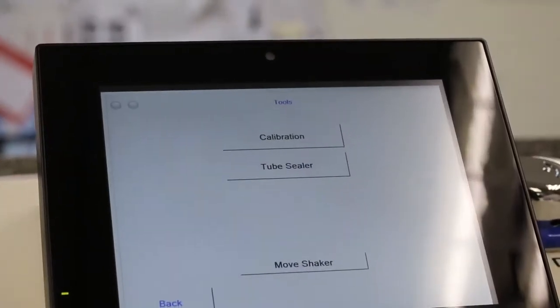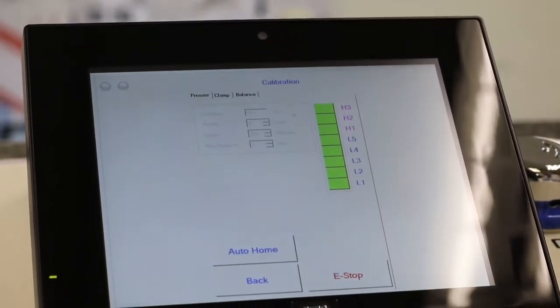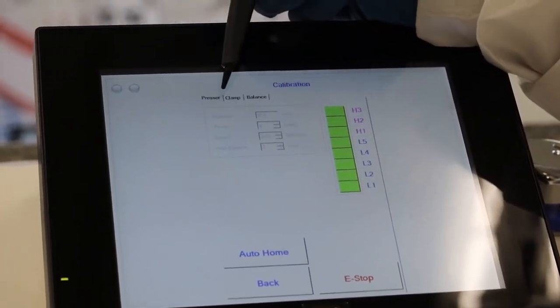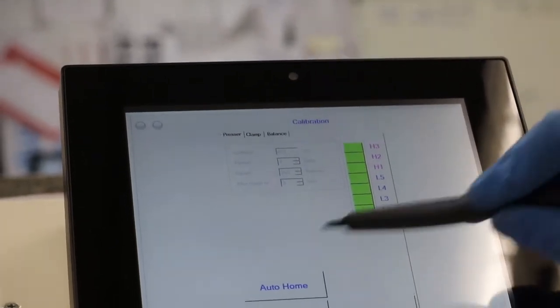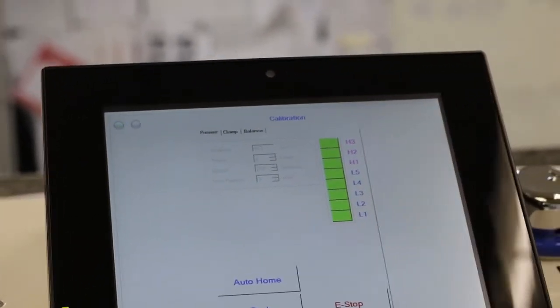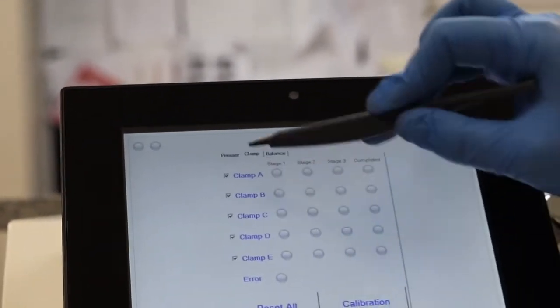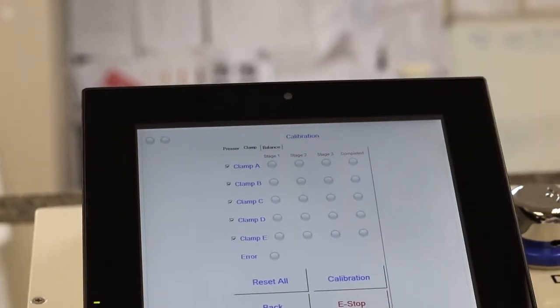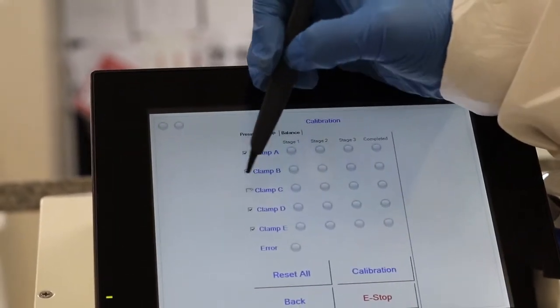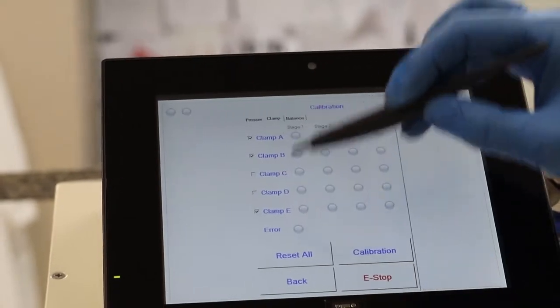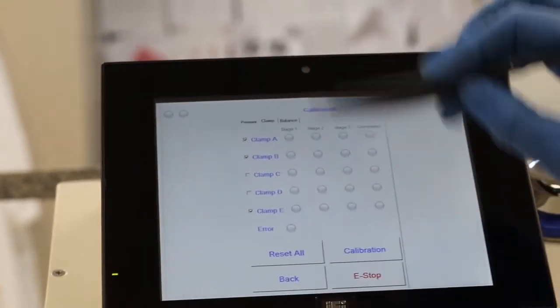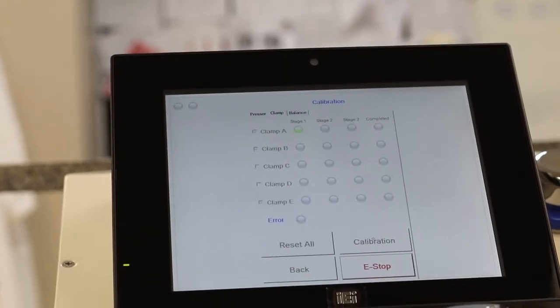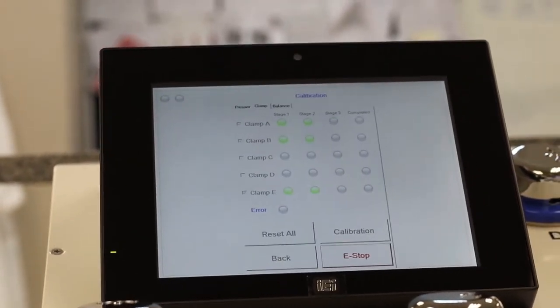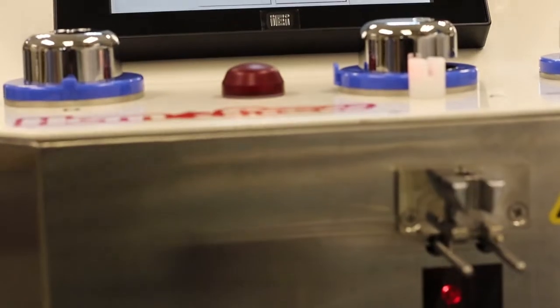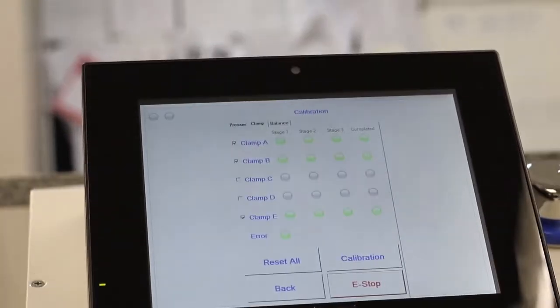That super user will be able to access the calibration files. You will see on the top, it's the pressure calibration. They can just press Auto Home and it will test the pressure calibration. You can go to clamps. All of the clamps are selected. We don't need C and D, so I'm going to unselect C and D. We only use A, B, and E. So then here, they can just do a calibration and all three clamps pass calibration.